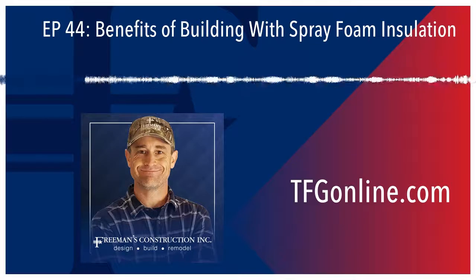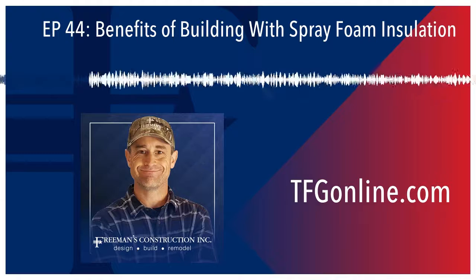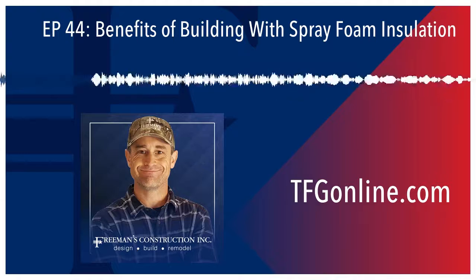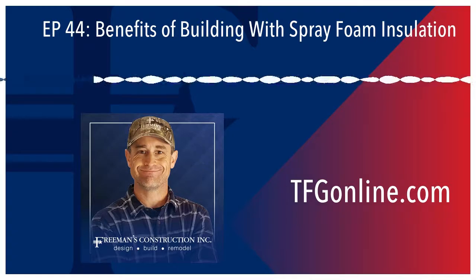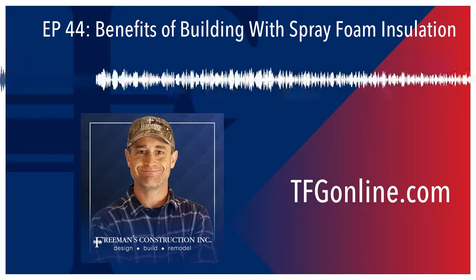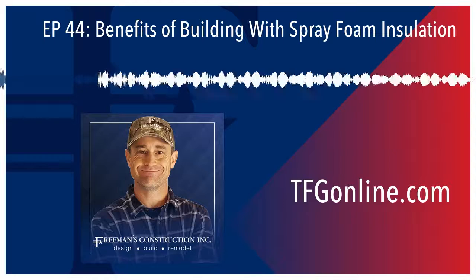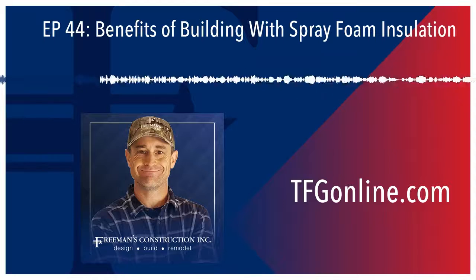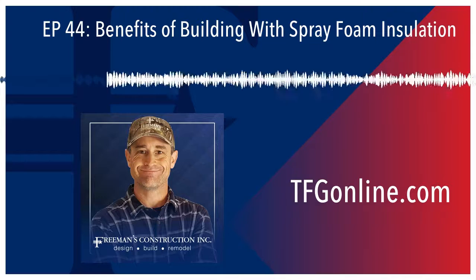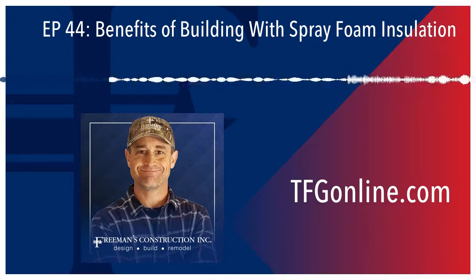When you do this, it's the way that you have to do it in wildfire areas now totally changes what you have to do. So these vents that we use a lot, we use Brandguard vents quite a bit, and these Brandguard vents have baffles in them, and it really reduces the net free air ventilation area that you get from these.